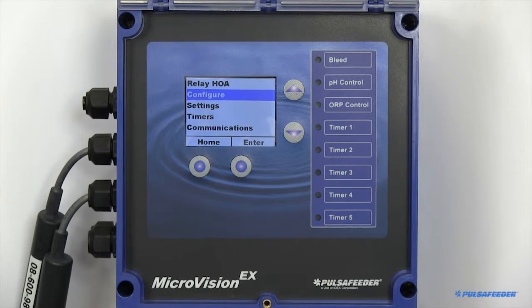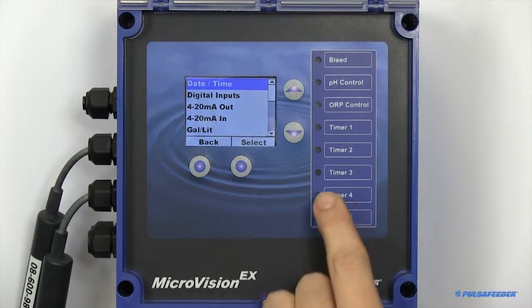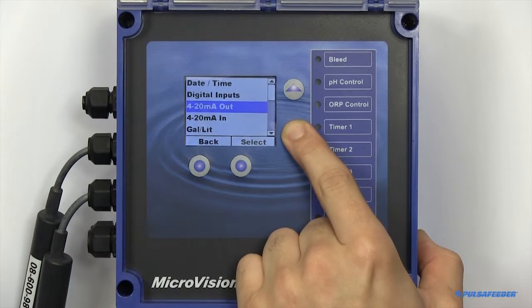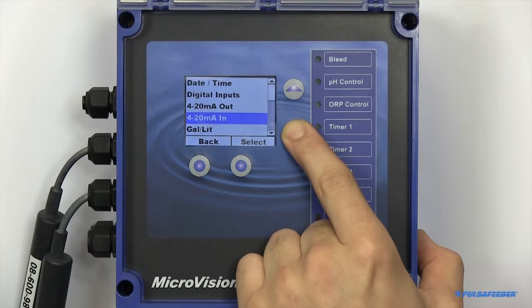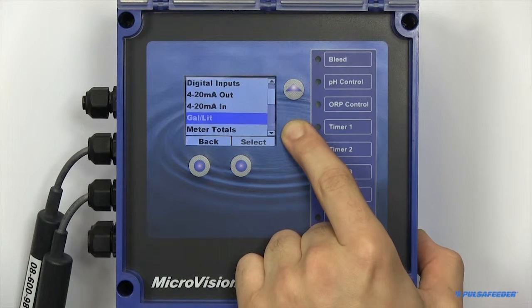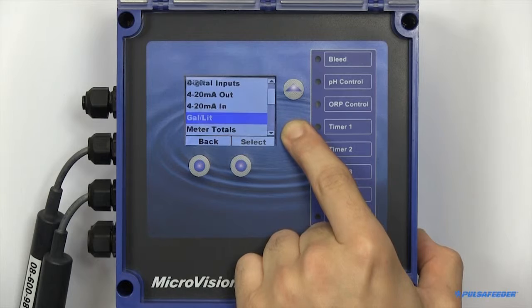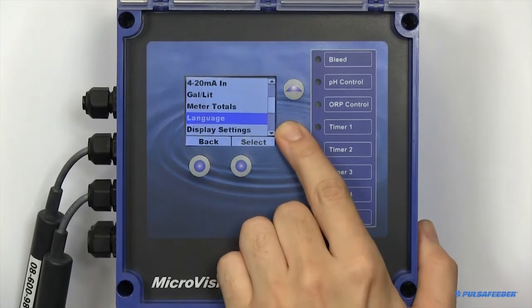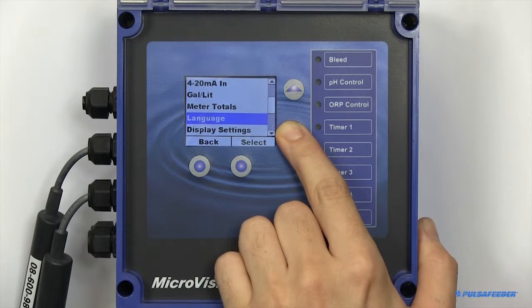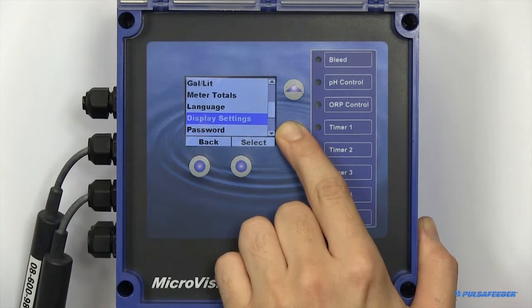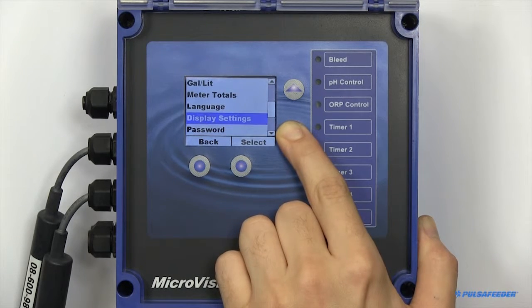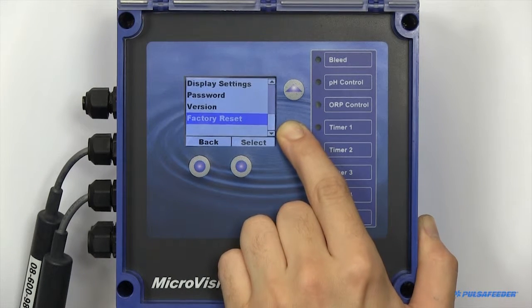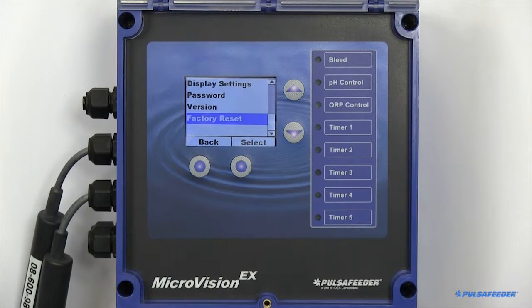The Configure menu is where you can access your date and time settings, adjust your digital inputs, enable or disable your 4-20 milliamp in and output functions, adjust your units, reset meter totals, change the language of the unit, configure display settings, enable software passwords, view the version of the software, as well as initialize a factory reset.